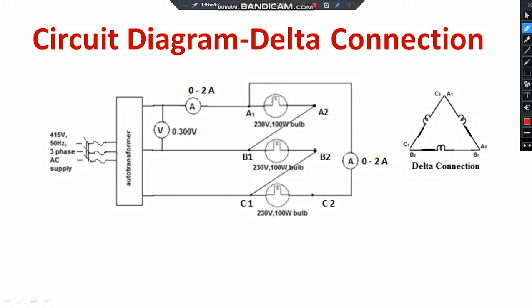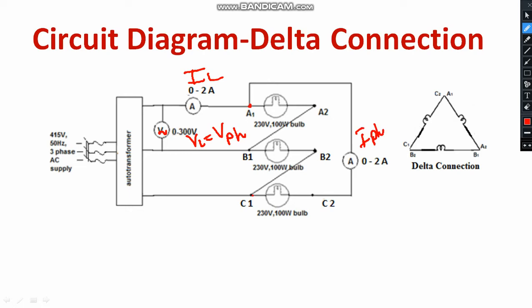Now regarding delta connection — A1A2, B1B2, C1C2 are the three coils. The ending of the first coil is connected to the beginning of the second coil, and the ending of the second coil is connected to the beginning of the third coil. There is no neutral point. This type of arrangement is known as delta connection. In case of delta connection, the voltmeter gives both line voltage and phase voltage — line voltage and phase voltage will be equal. The ammeter gives the line current, and there is a separate phase current. You will be identifying the relation between line current and phase current.